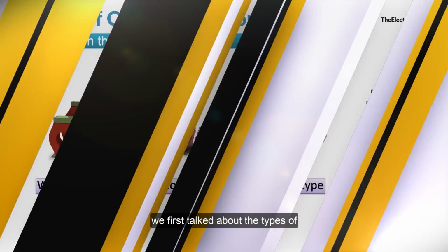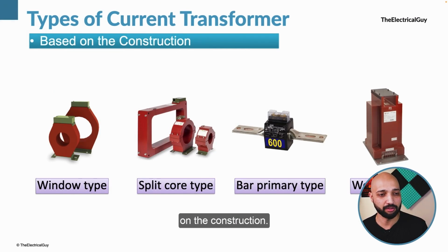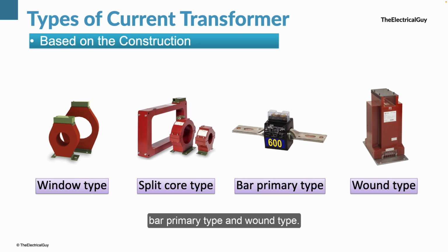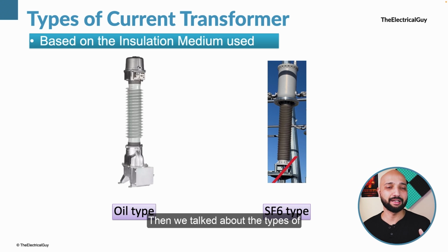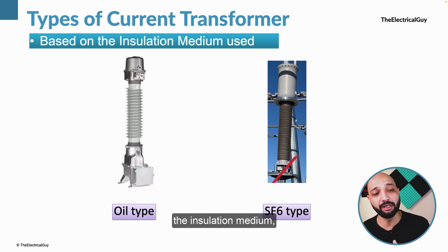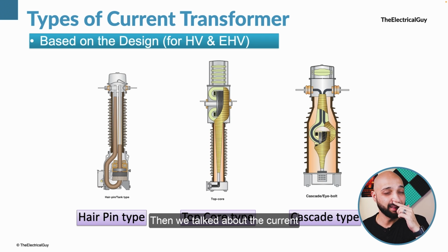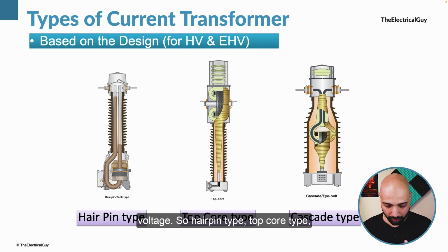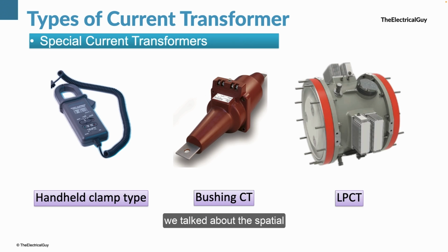Just to quickly summarize the video, we first talked about the types of current transformer based on the construction. So we talked about window type, split core type, bar primary type and wound type. Then we talked about the types of current transformer based on the insulation medium, oil type and SF6 type. Then we talked about the current transformer based on the design, which is specific to high and extra high voltage: hairpin type, top core type and the cascade type.